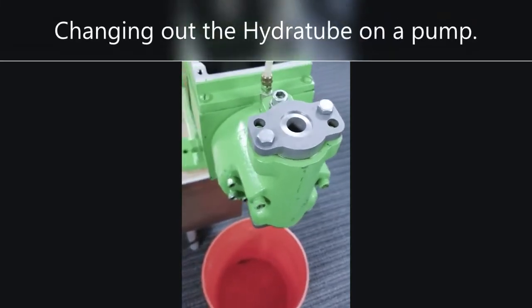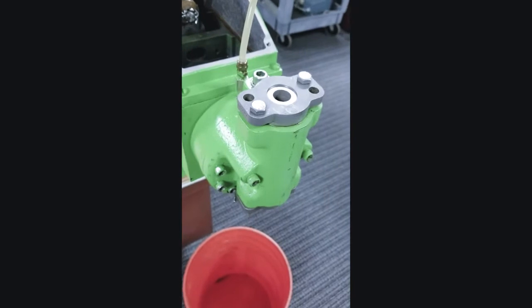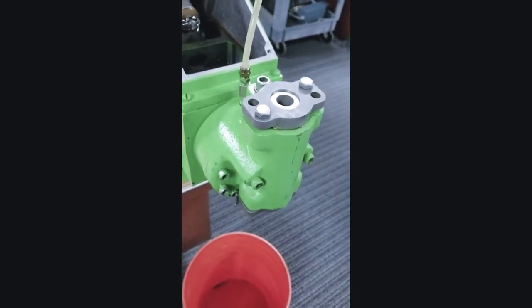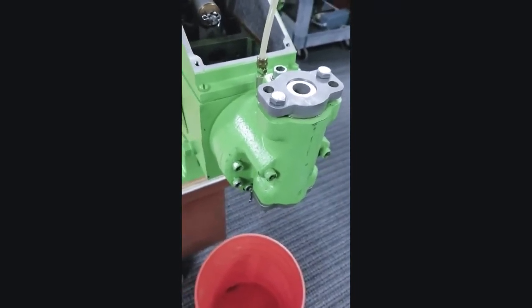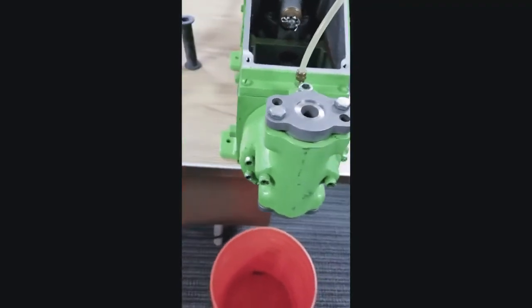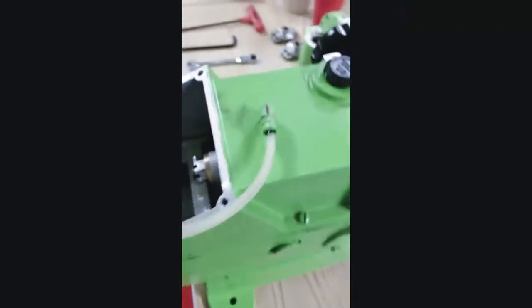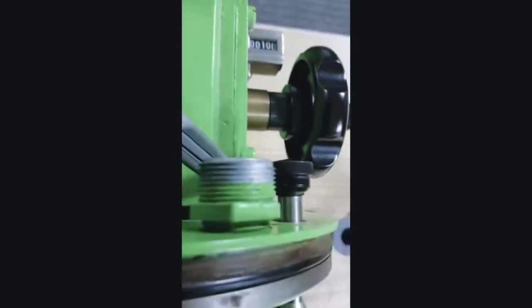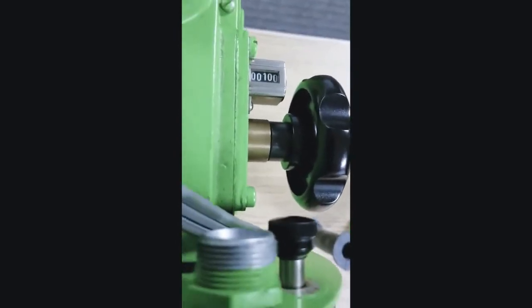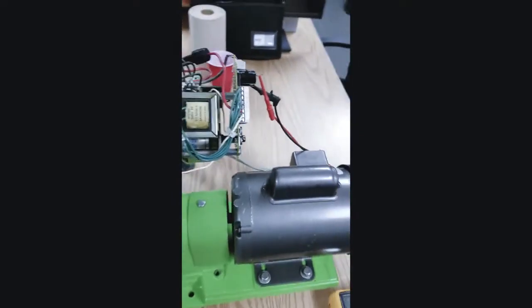Good morning. Today we are going to be changing out a Hydratube on a Pulsa 7120 Hydratube pump. So in order to do this, the first things we're going to need to do is set our stroke setting to 100% on the dial, and then we're going to shut the pump down and isolate it from power.